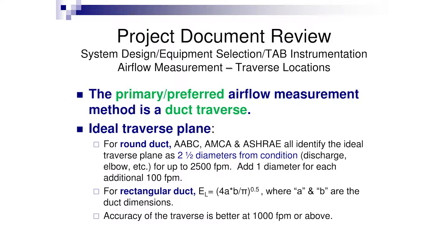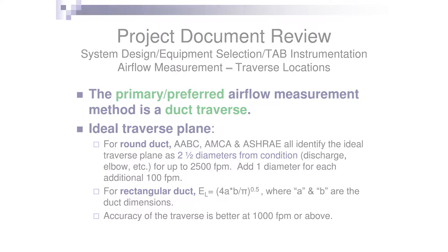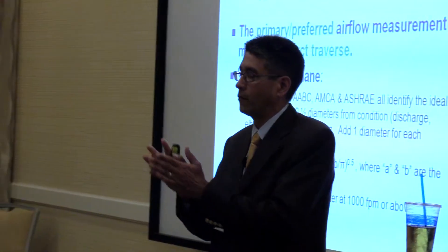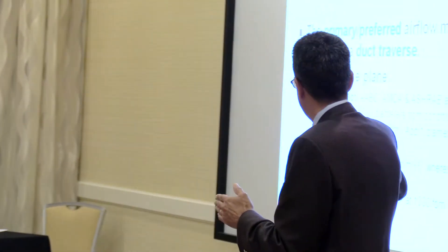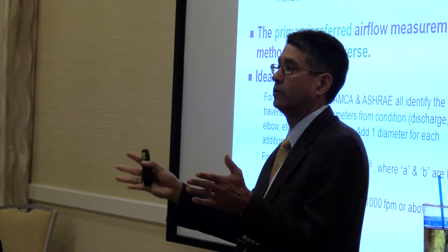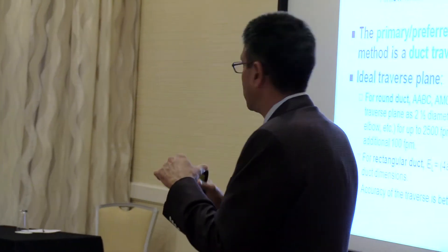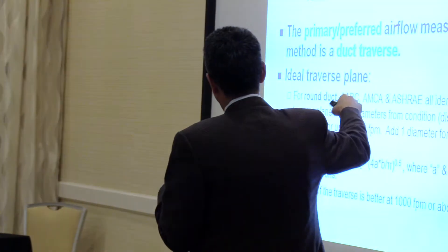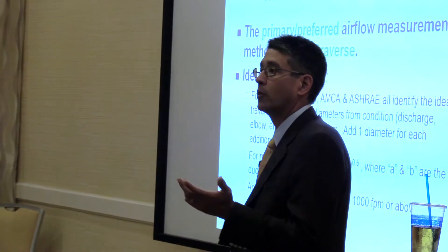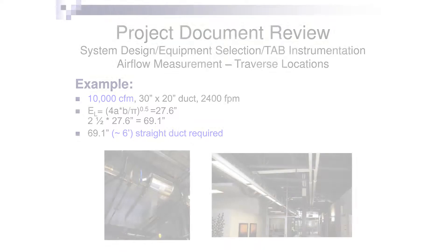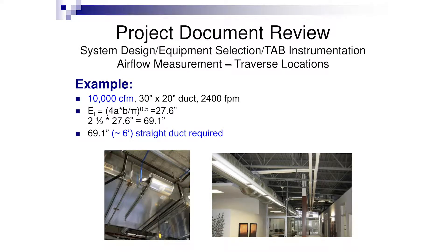Keep in mind the primary preferred method for air flow measurement is a duct traverse — that's our most accurate means of providing an airflow measurement. You want 2.5 diameters from any condition for an ideal traverse plane. For rectangular duct, use your equation to get the equivalent length; for round duct, it's just the round duct diameter. The velocity should be better than 1,000 feet per minute for more accurate readings.